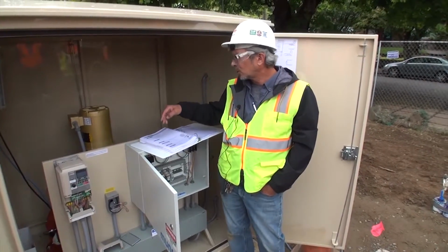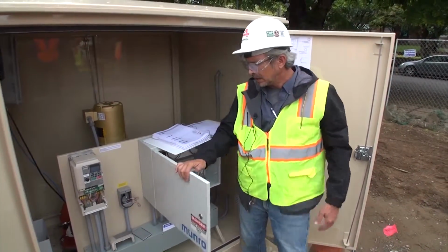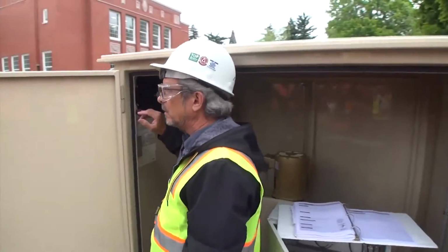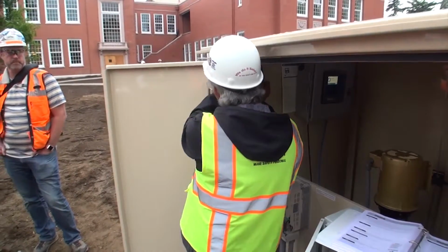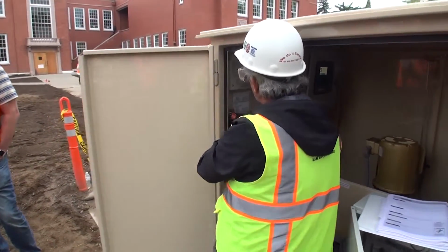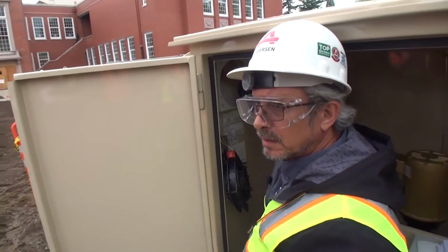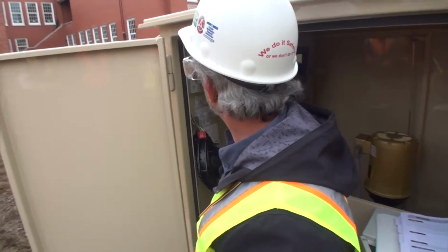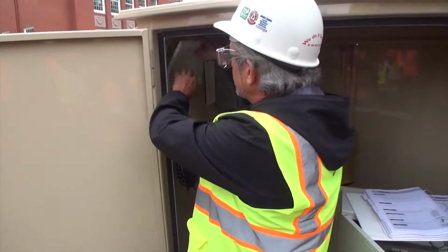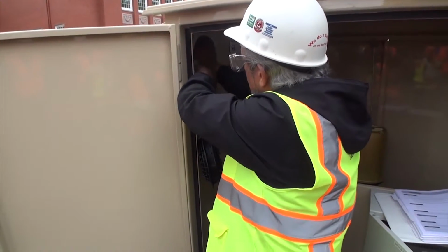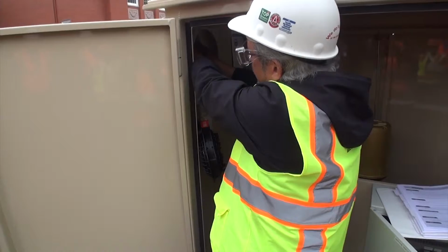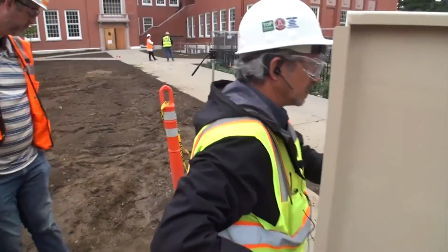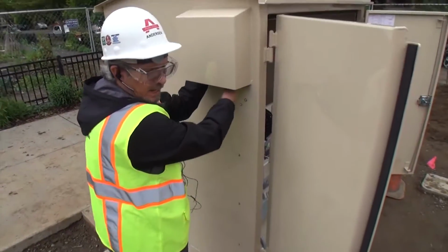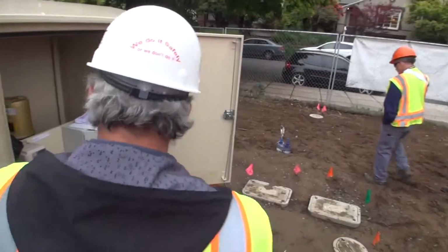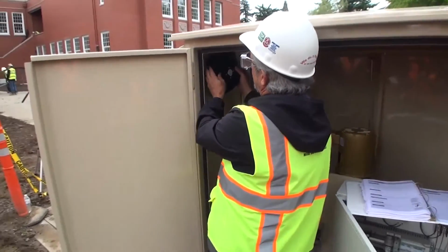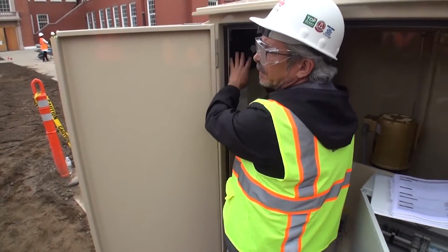The cooling, we're talking about these fans to keep the panel cool. This particular fan here is difficult to get out from inside the rain shield, so I recommend you just give this a little turn counterclockwise, take it off, push this out, take the foam out, and you can clean it. Put it back in the same way you took it out. Make sure it fits in the receptor. Push it back in at the top. It pivots at the bottom. Put this back up here. Line up the holes. Snap it back in place.